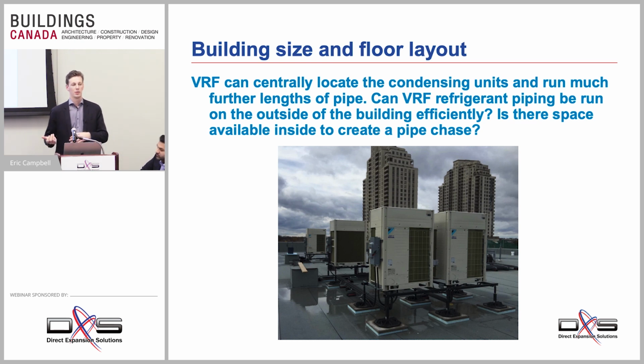However, now that you've got all those pipes, so you've got your outdoor units up on the roof, you need a place to route those pipes. So it might be on the outside of the building. We've looked at doing that in certain applications. Otherwise, you need some sort of pipe chase internal to the building next to your elevator shaft or something. You need space to run those pipes.